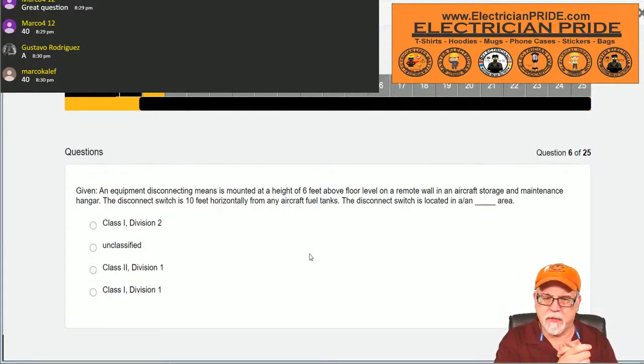All right, notice it says given. It says an equipment disconnection means is mounted at a height of 6 feet above the floor level on a remote wall in an aircraft storage and maintenance hangar. The disconnect switch is 10 feet horizontally from the aircraft fuel tank. So it's the disconnect itself that is 10 feet horizontally from the aircraft fuel tank. The disconnect switch is located in a blank area. Is it Class 1 Division 2? Is it unclassified? Is it Class 2 Division 1? Or is it a Class 1 Division 1? You have an A, B, C, or D.